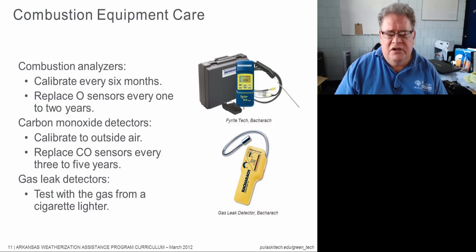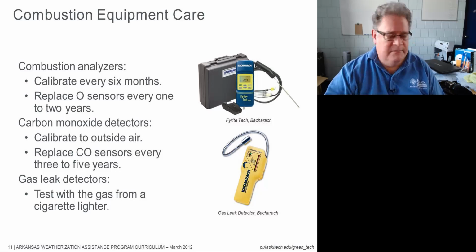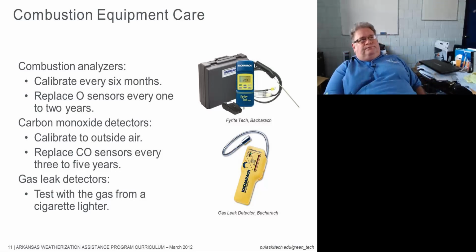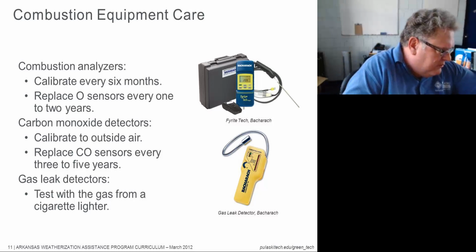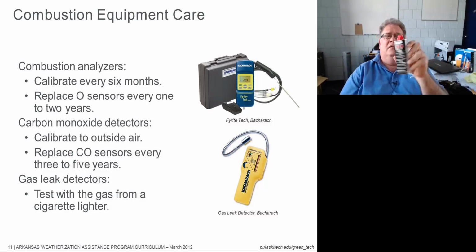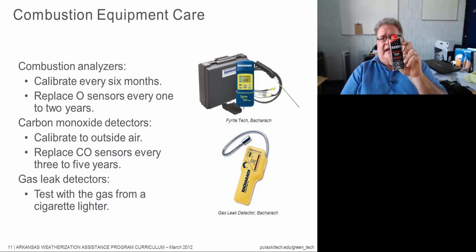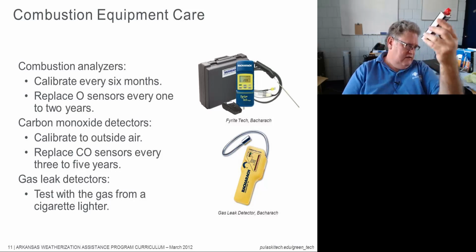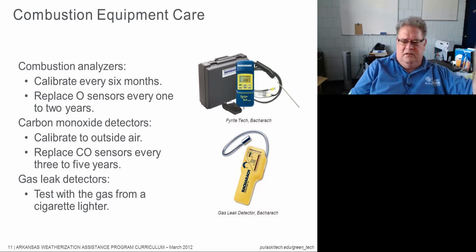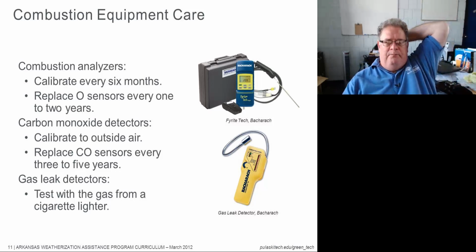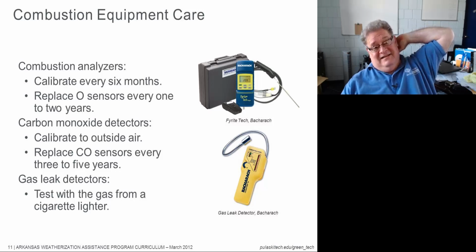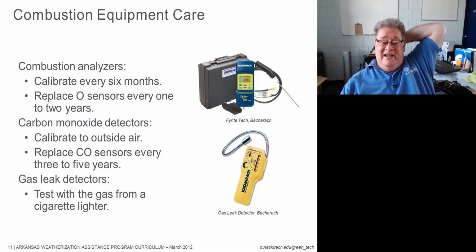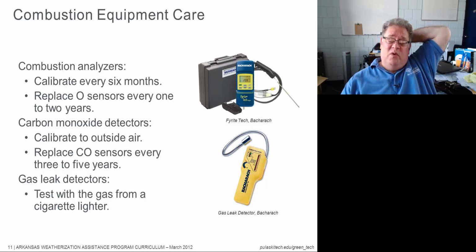Gas leak detectors, you want to test with the gas from a cigarette lighter. And what they're talking about there is if you have an old-fashioned cigarette lighter, one that burns this stuff right here, okay, a lighter fluid. Gas leak detectors will detect almost anything that is combustible, including lighter fluid. So that's a good way to test it.